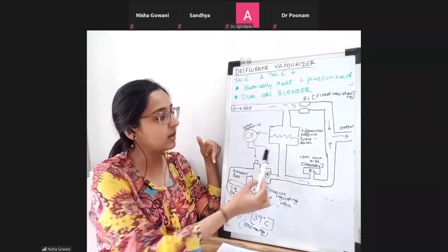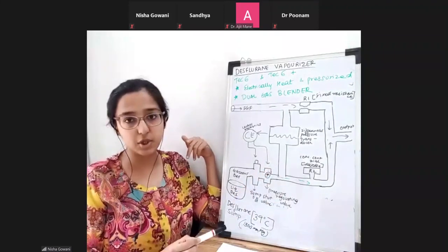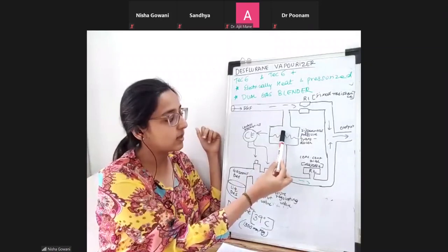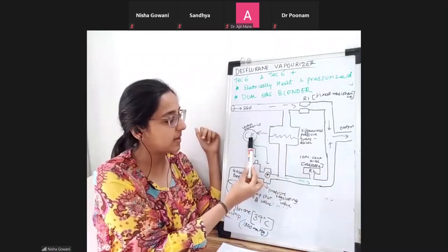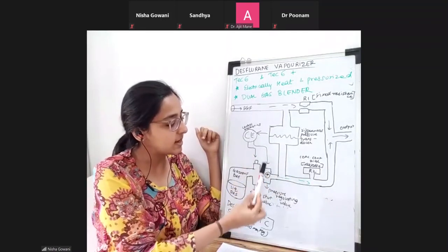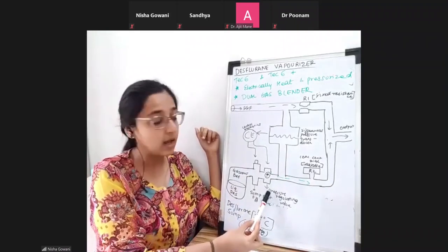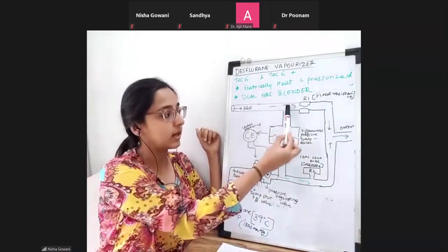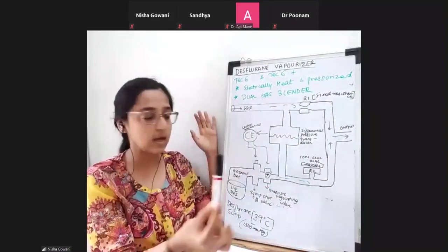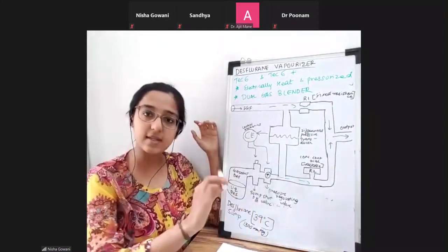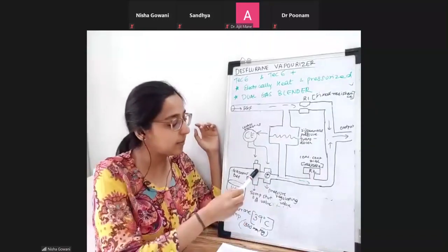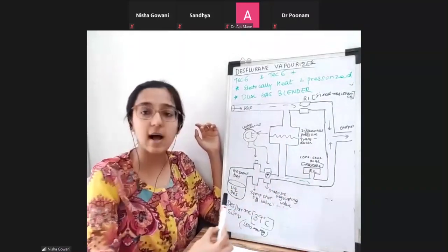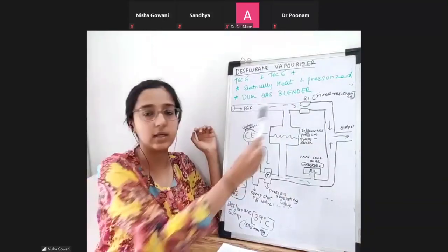They are interacting with each other with the help of this differential pressure transducer. So the pressure is sensed over here. That pressure value is given over here. The message is passed on over here. This sends a message to the pressure regulating valve. The pressure regulating valve understands that the pressure in this circuit above is X. So this pressure regulating valve will set itself such that the vapor pressure which leaves out will be equal to the pressure over here.